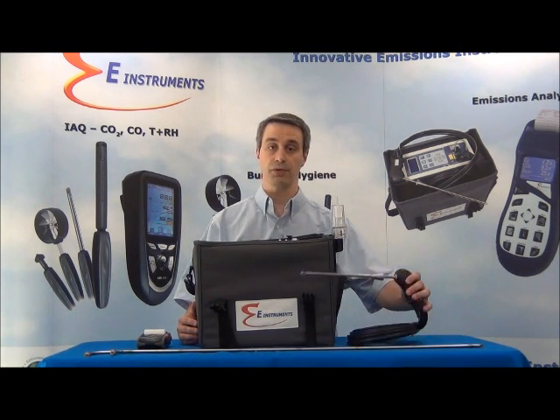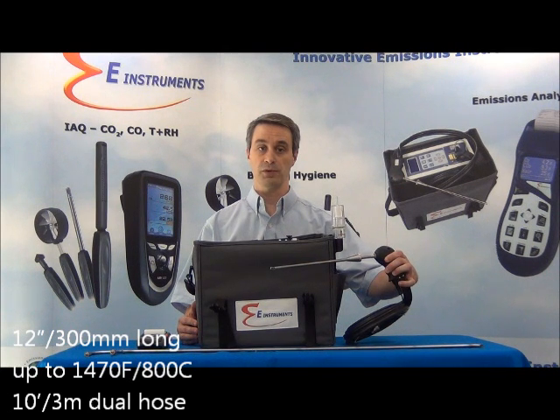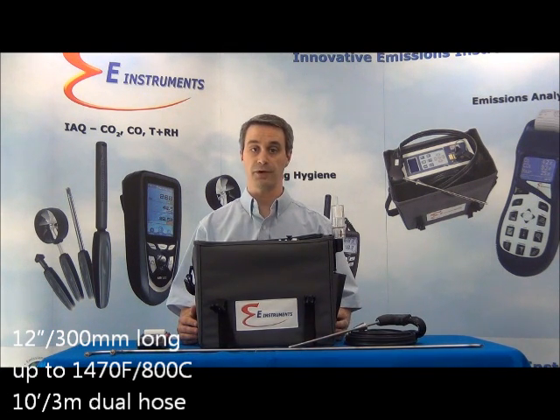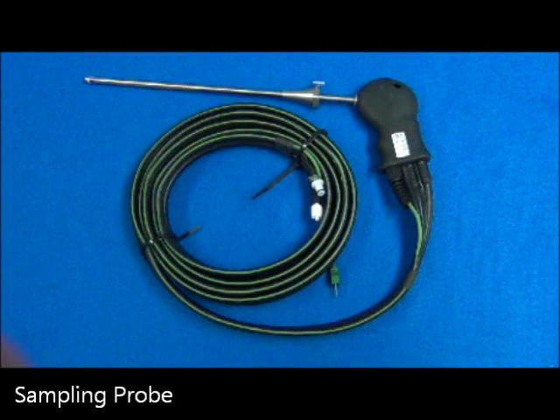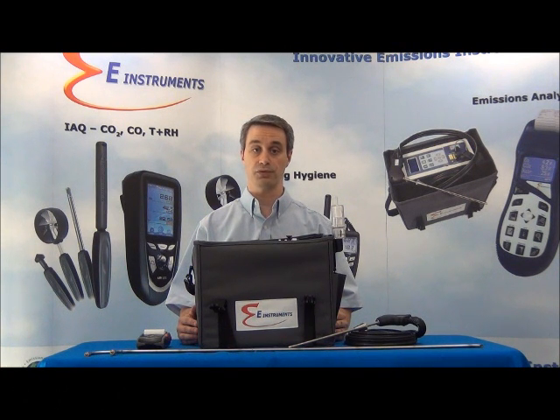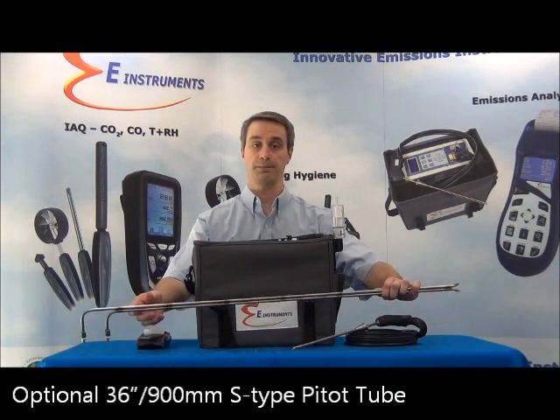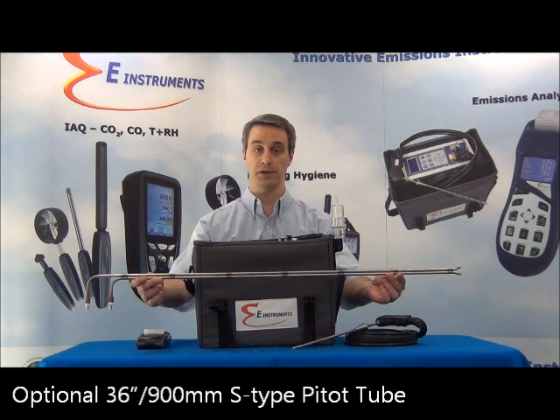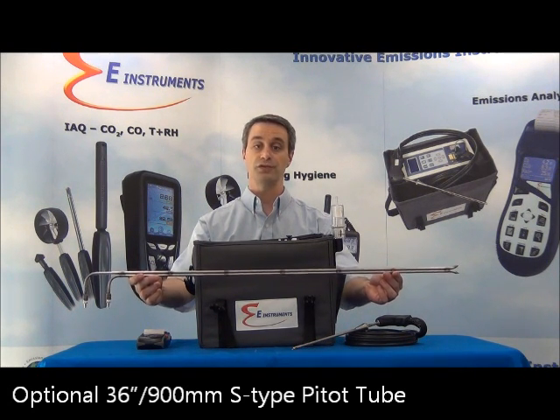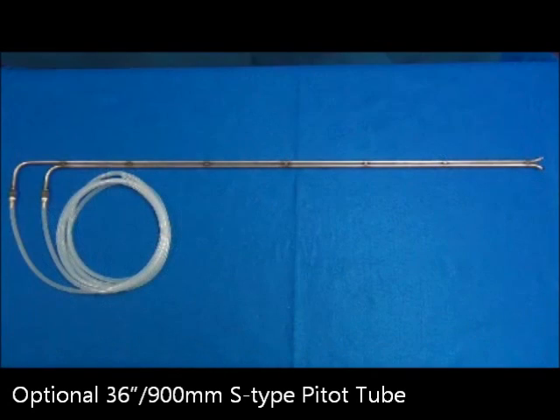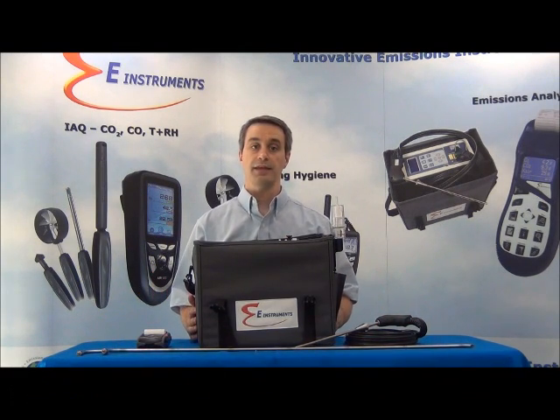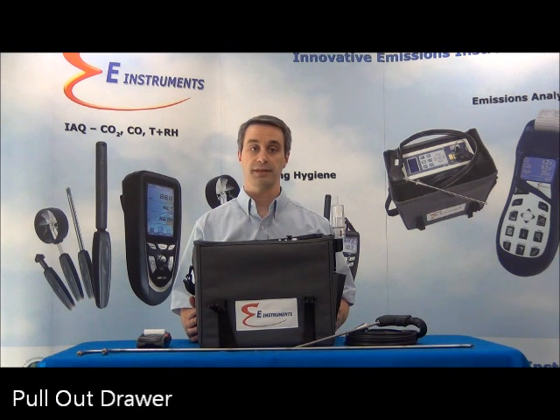The standard gas sampling probe is 12 inches, which is 300 millimeters long, and it's good up to 1470 F, 800 degrees C, and includes a 10-foot, 3-meter dual hose. Longer and higher temperature probes and hose extensions are also available with the E5500. An optional S-type pitot tube, which is 36 inches, 900 millimeters long, can be used with the E5500 to measure stack gas velocity and allow for mass flow rate emissions. The E5500 has a pull-out drawer that allows for easy access to check and change the internal filters as needed.